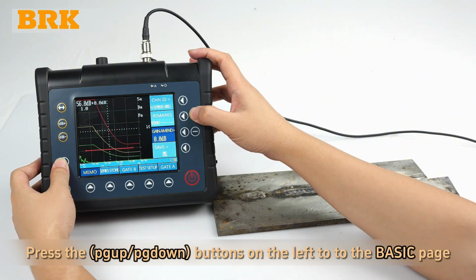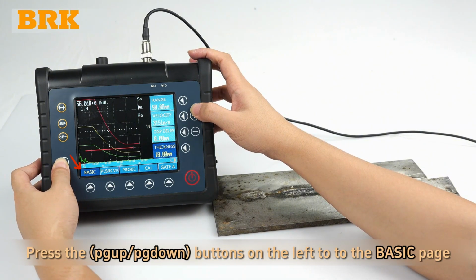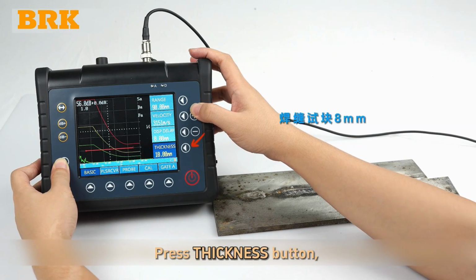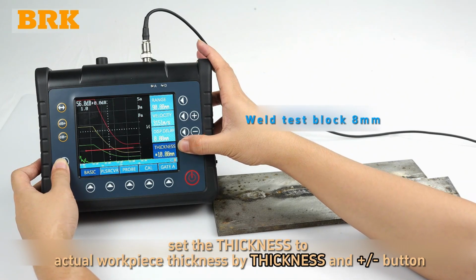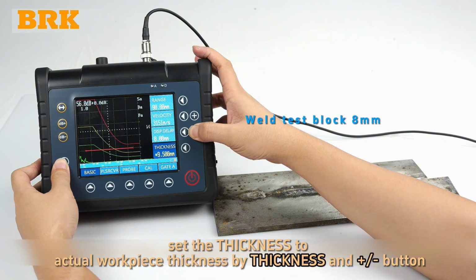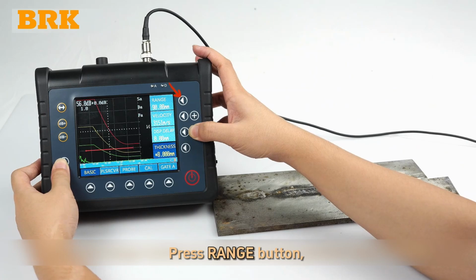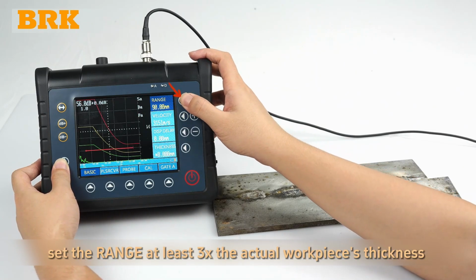Press the page up or page down buttons on the left to the basic page. Press thickness button. Set the thickness to actual workpiece thickness by thickness and plus and minus button. Press range button. Set the range at least 3 times the actual workpiece's thickness.